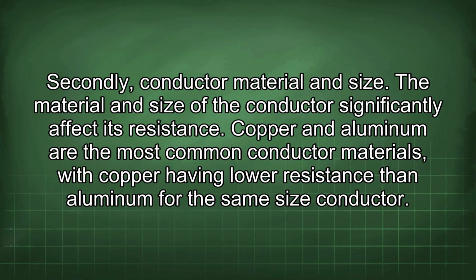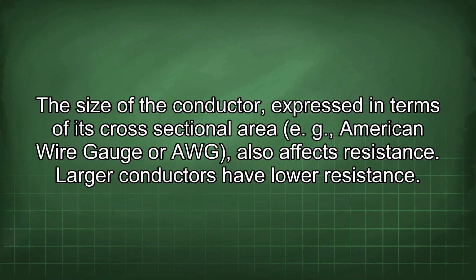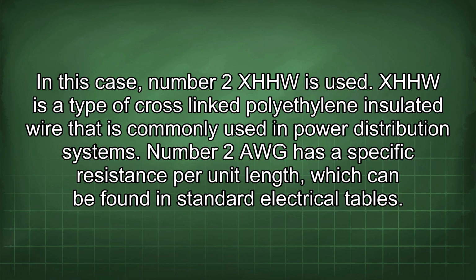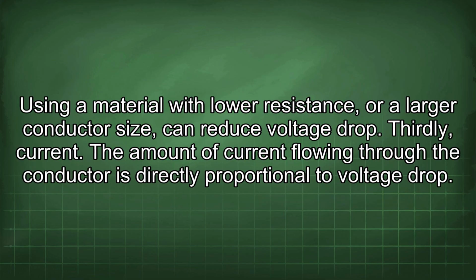Secondly, conductor material and size. The material and size of the conductor significantly affect its resistance. Copper and aluminum are the most common conductor materials, with copper having lower resistance than aluminum for the same size conductor. The size of the conductor, expressed in terms of its cross-sectional area, e.g., American wire gauge or AWG, also affects resistance. Larger conductors have lower resistance. In this case, number 2 XHHW is used. XHHW is a type of cross-linked polyethylene insulated wire that is commonly used in power distribution systems. Number 2 AWG has a specific resistance per unit length, which can be found in standard electrical tables. Using a material with low resistance or a larger conductor size can reduce voltage drop.